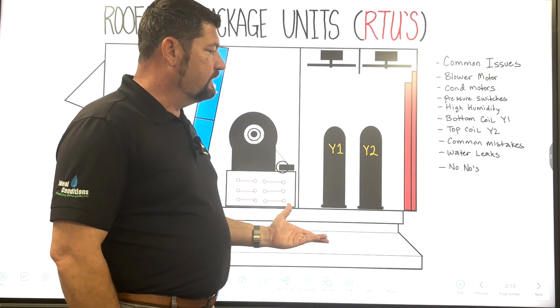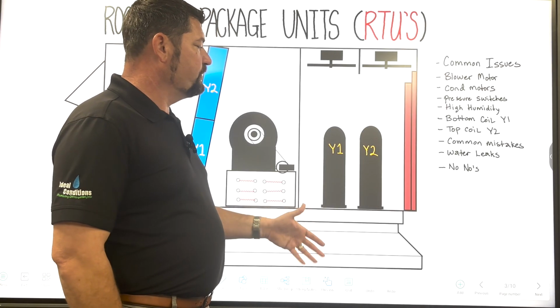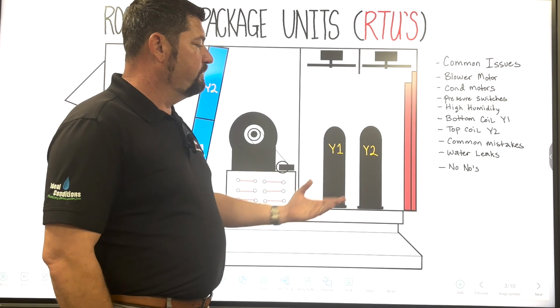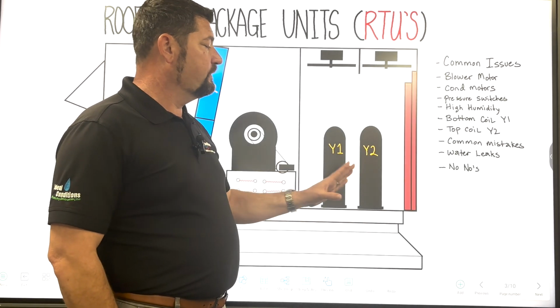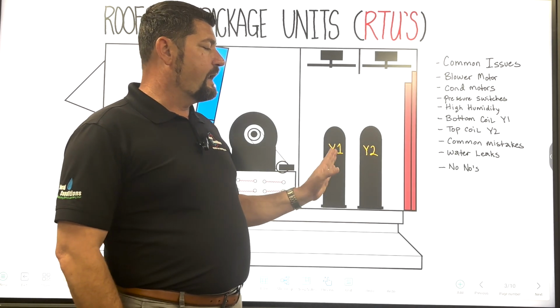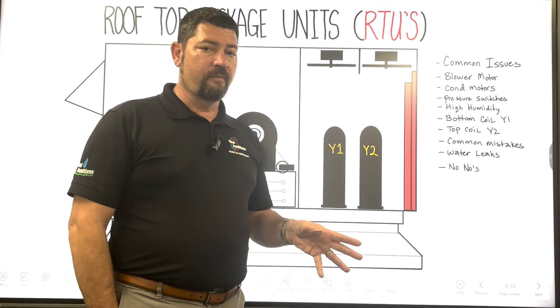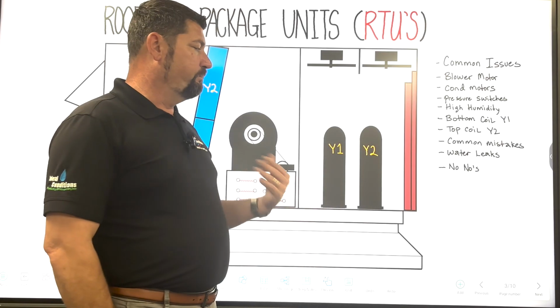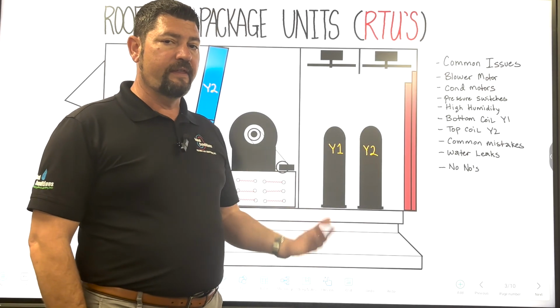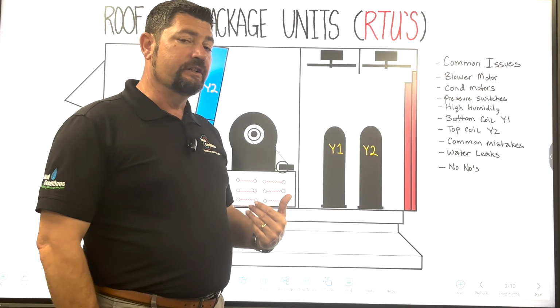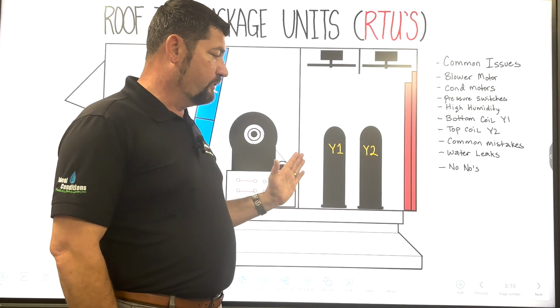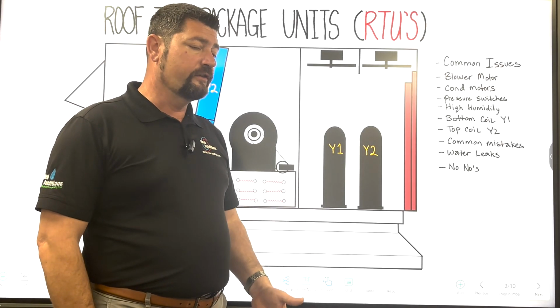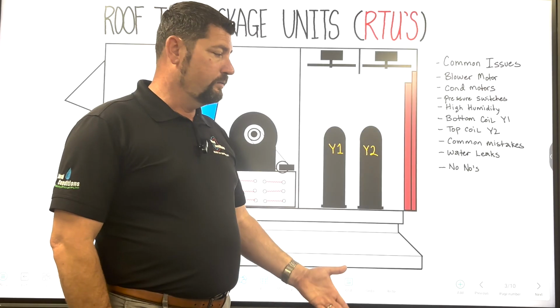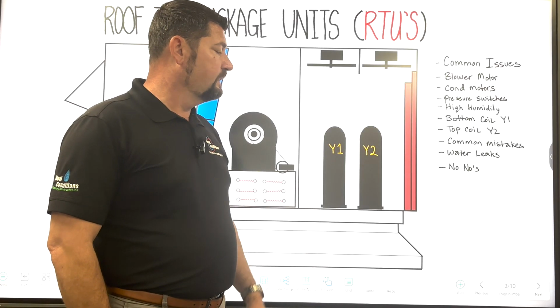At the end of the day, it's however the manufacturer wanted to make that. What we see a lot of times are people will wire the Y1 and Y2 to both come on at the same time. That's a big surge in power when that thing first comes on. That's not good for the equipment. That's not good for the fuses that are there to protect that equipment.